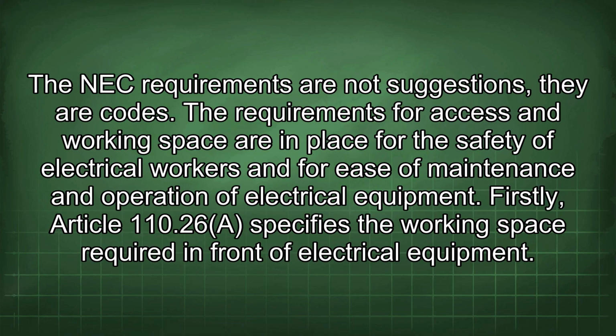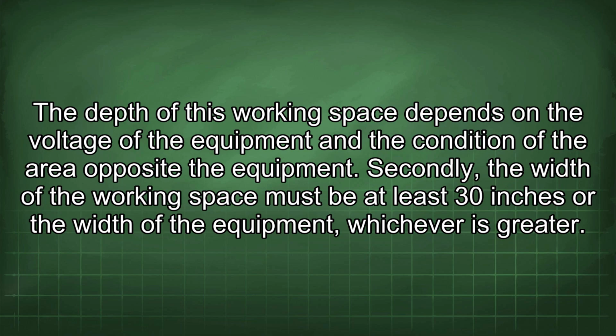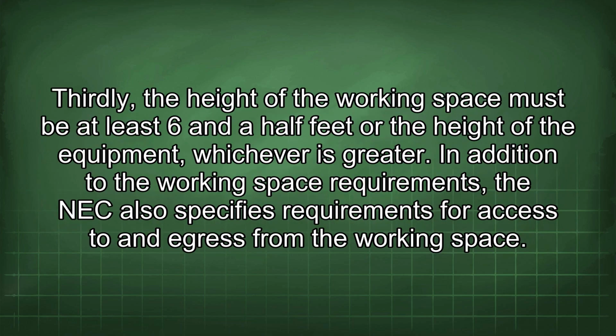The NEC requirements are not suggestions, they are codes. The requirements for access and working space are in place for the safety of electrical workers and for ease of maintenance and operation of electrical equipment. Firstly, Article 110.26 specifies the working space required in front of electrical equipment. The depth of this working space depends on the voltage of the equipment and the condition of the area opposite the equipment. Secondly, the width of the working space must be at least 30 inches or the width of the equipment, whichever is greater. Thirdly, the height of the working space must be at least 6.5 feet or the height of the equipment, whichever is greater.